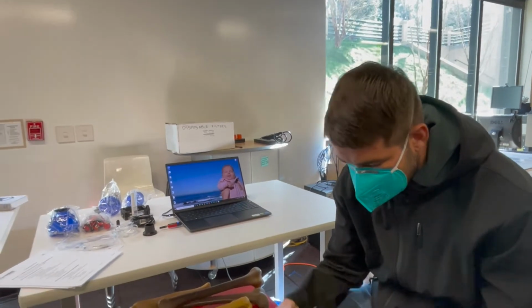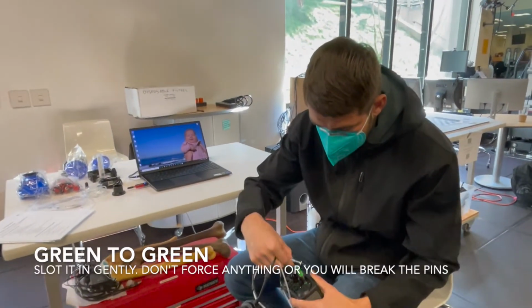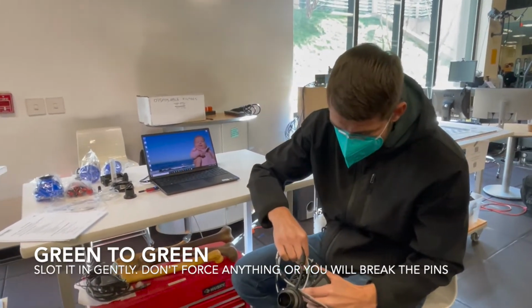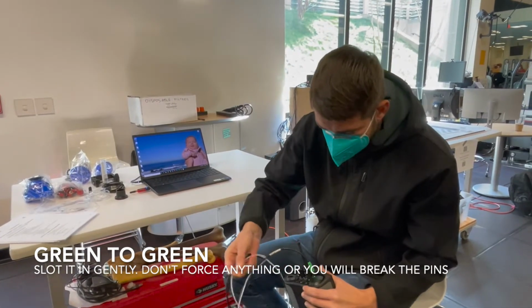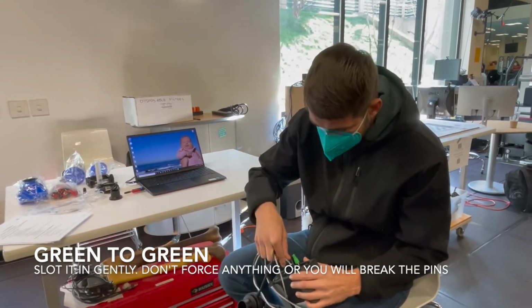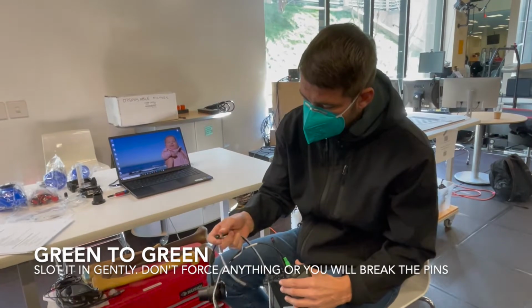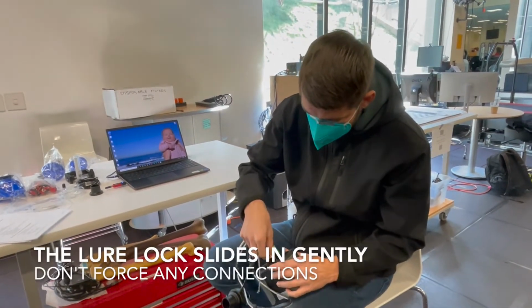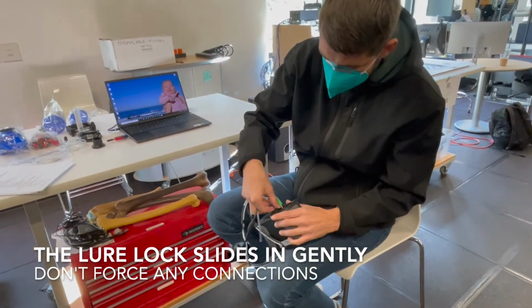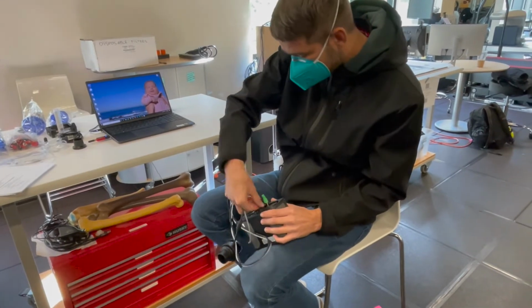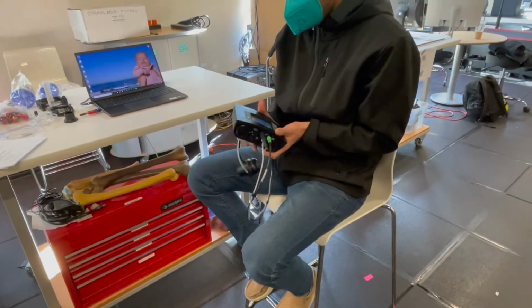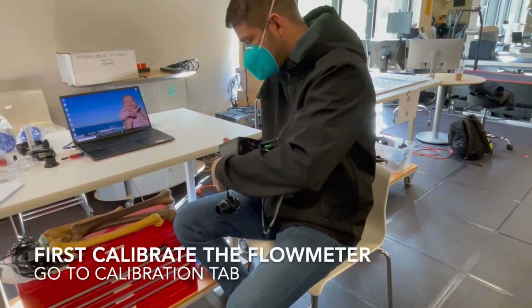So green to green, and it's labeled, so that should be pretty straightforward. If it's not sliding right in, just rotate it, and it'll find its slot. This is just like a luer lock, so you just stick it on and it'll turn freely. It won't put any tension in the line. And like I said, the first thing we're going to do is calibrate the flow meter.